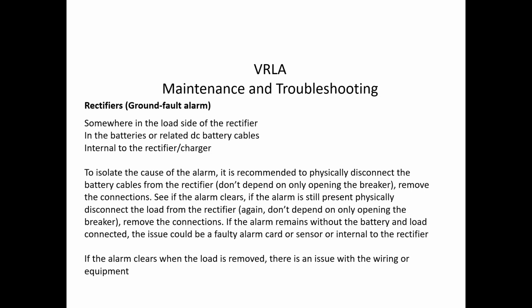People are usually quick to look at the battery, and that's not without cause, because a ground fault alarm within a battery can happen depending on how that battery is maintained. So sloppy housekeeping, when they're rewatering, again, this really goes back more to the flooded batteries, where technicians are periodically reintroducing water into the electrolyte. With bad housekeeping, they'll have a spill or something around the battery, or they're also prone to post-seal or jar cover leaks, and acid by nature will creep and get to the rack at some point and cause a ground fault indication at the battery. So that's why people usually look at the battery right away.